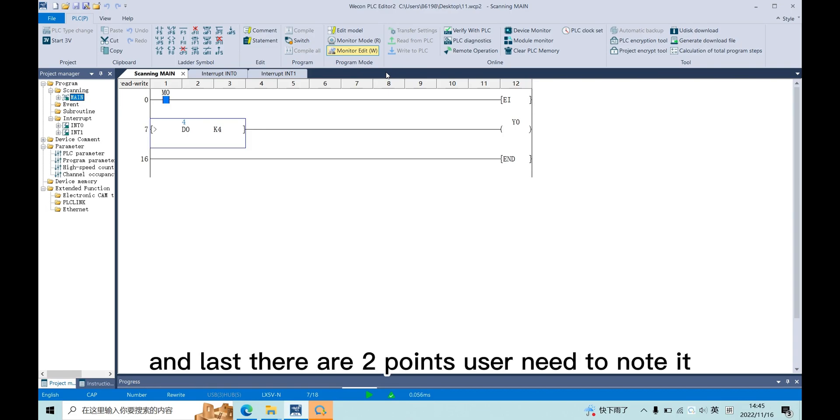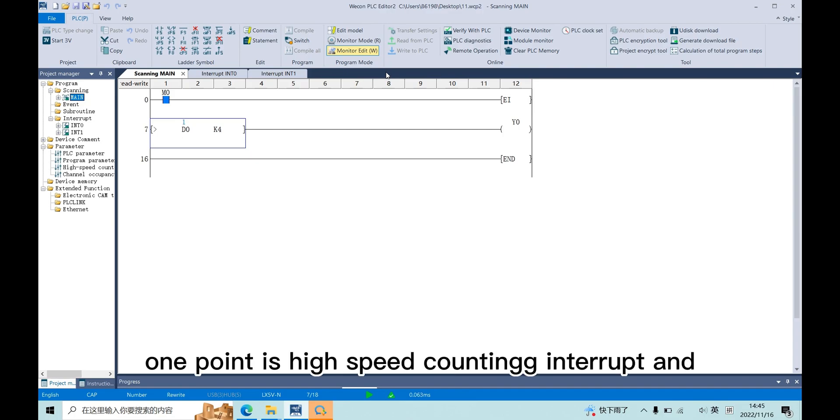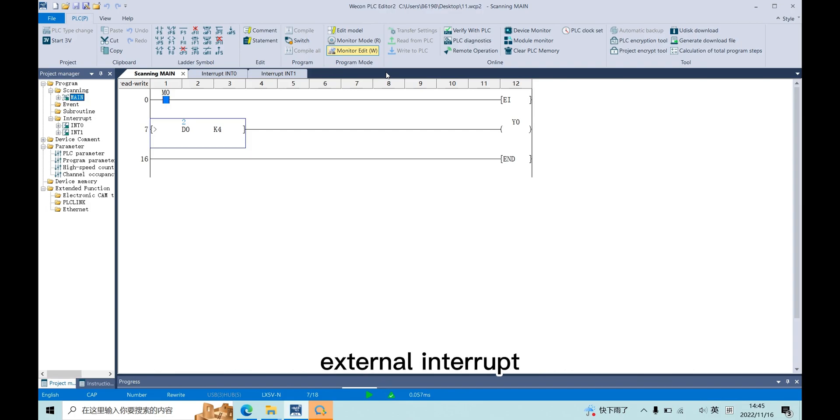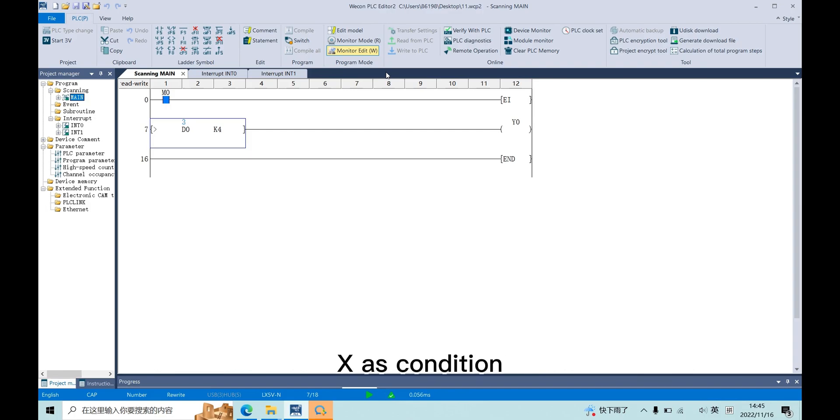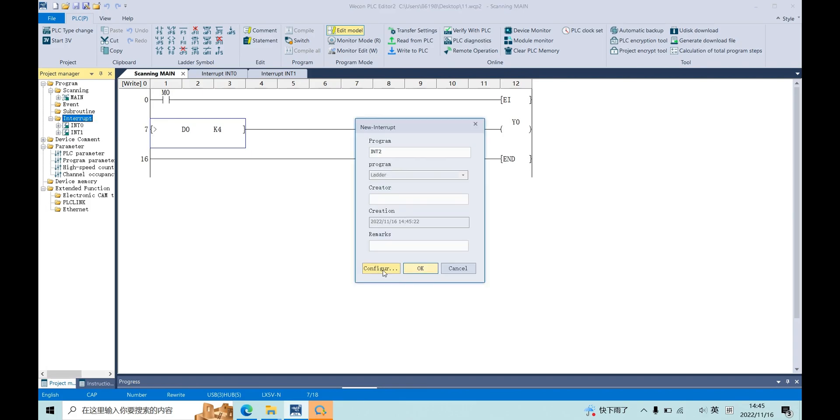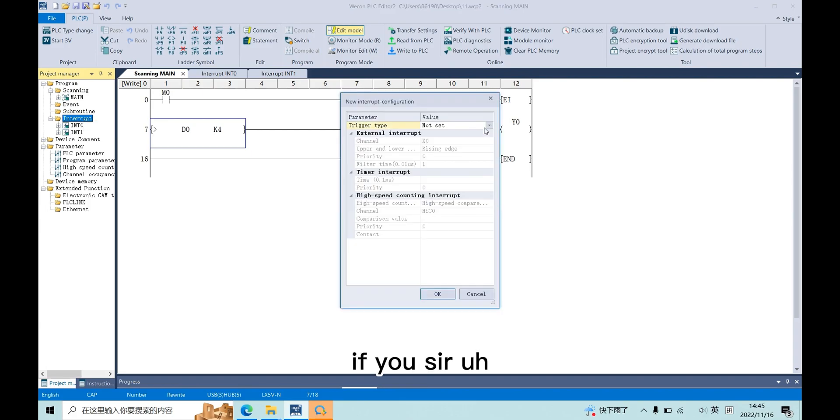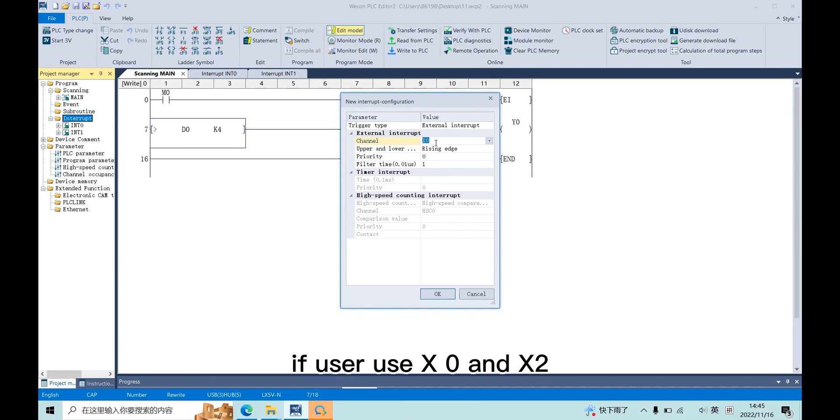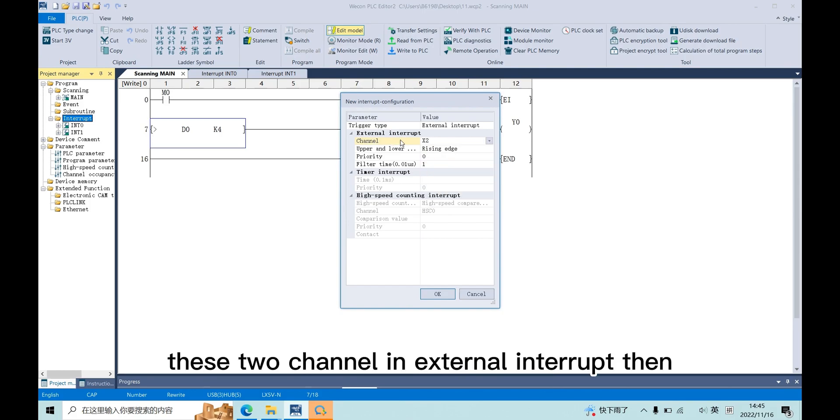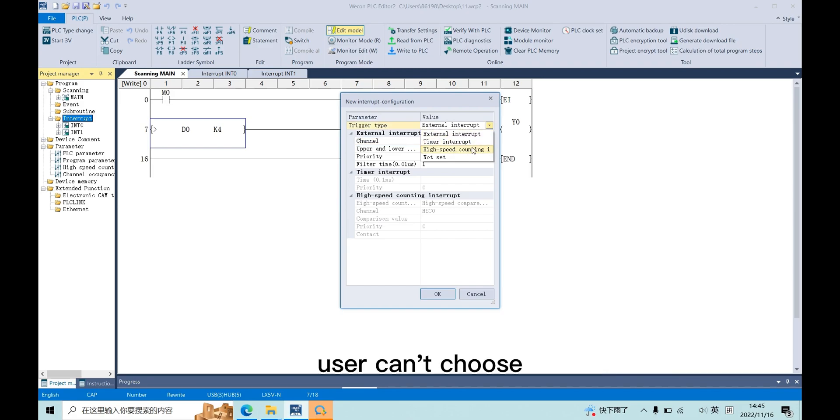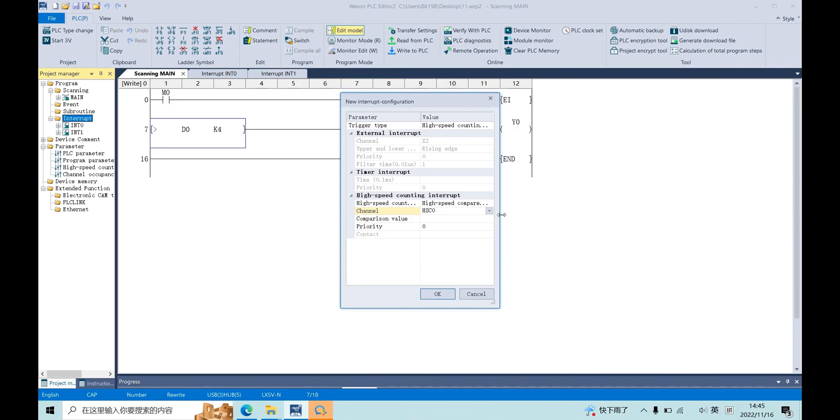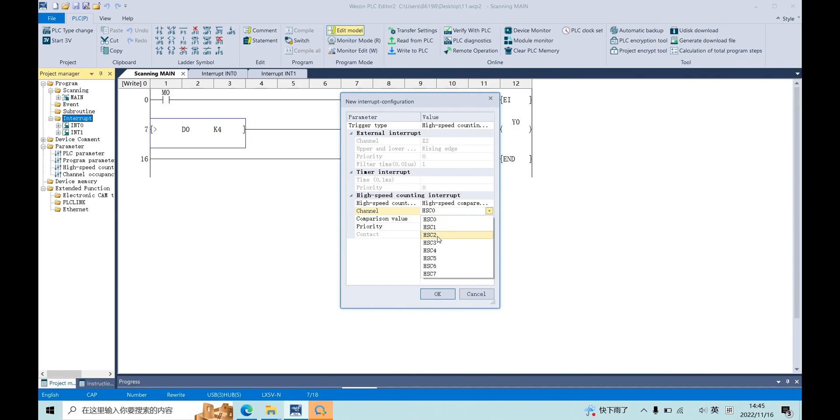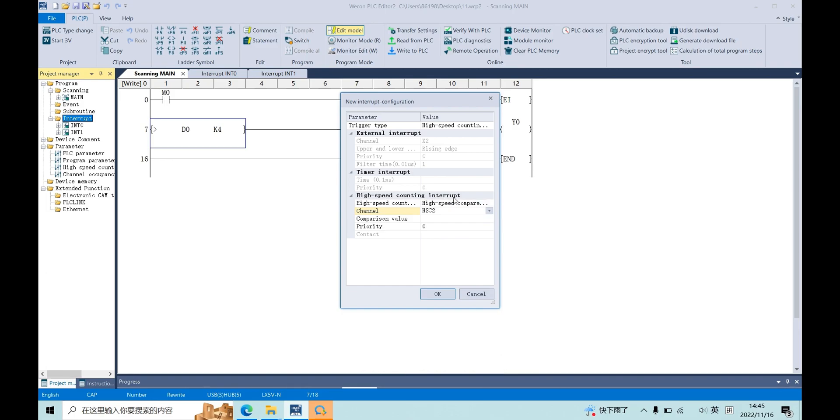And last, there are two points users need to note. One point is high-speed counting interrupt and external interrupt can't use the same X as condition. For example, if user uses X0 and X2 in external interrupt, then user can't choose HSC0 and HSC2 in high-speed counting interrupt.